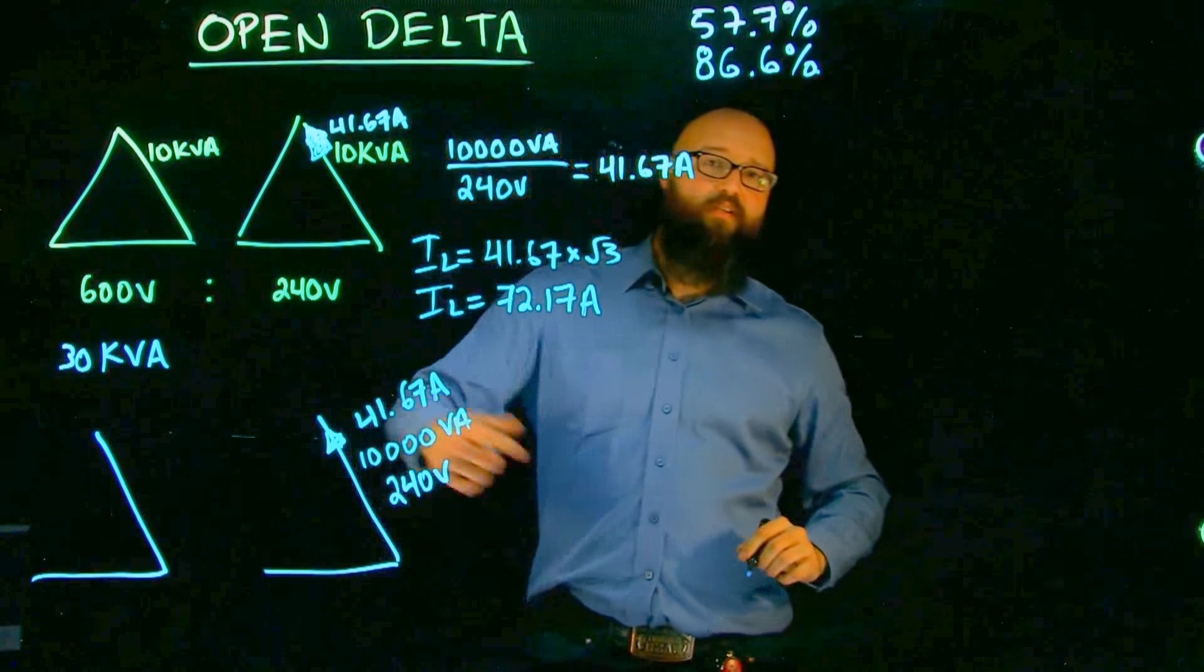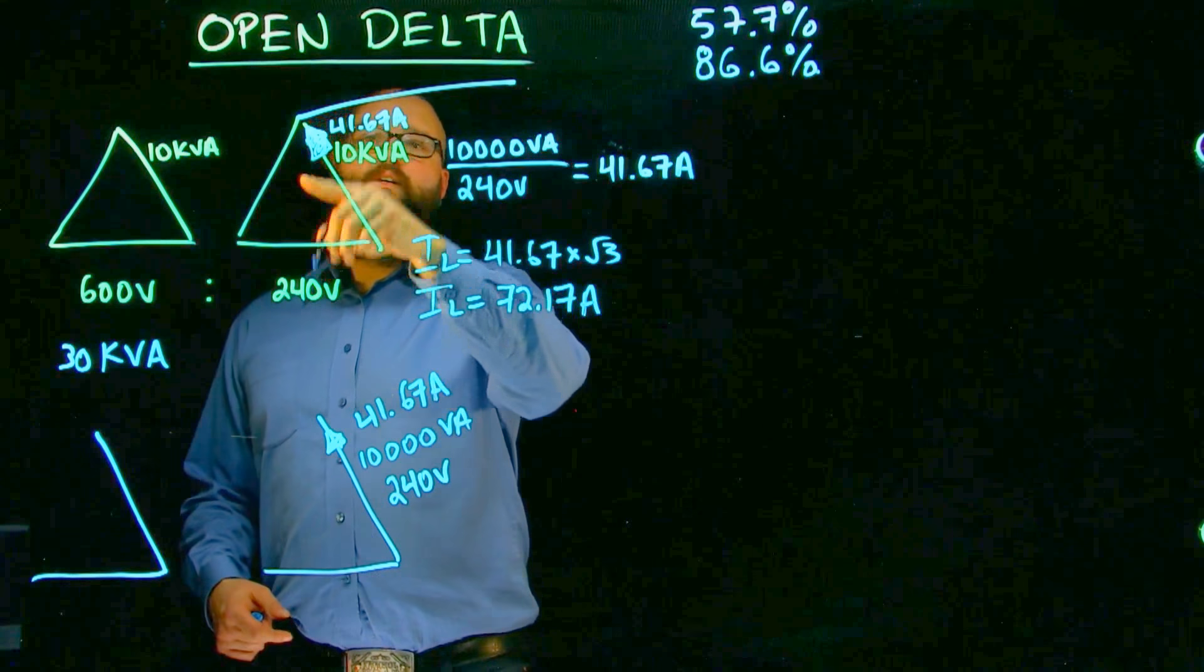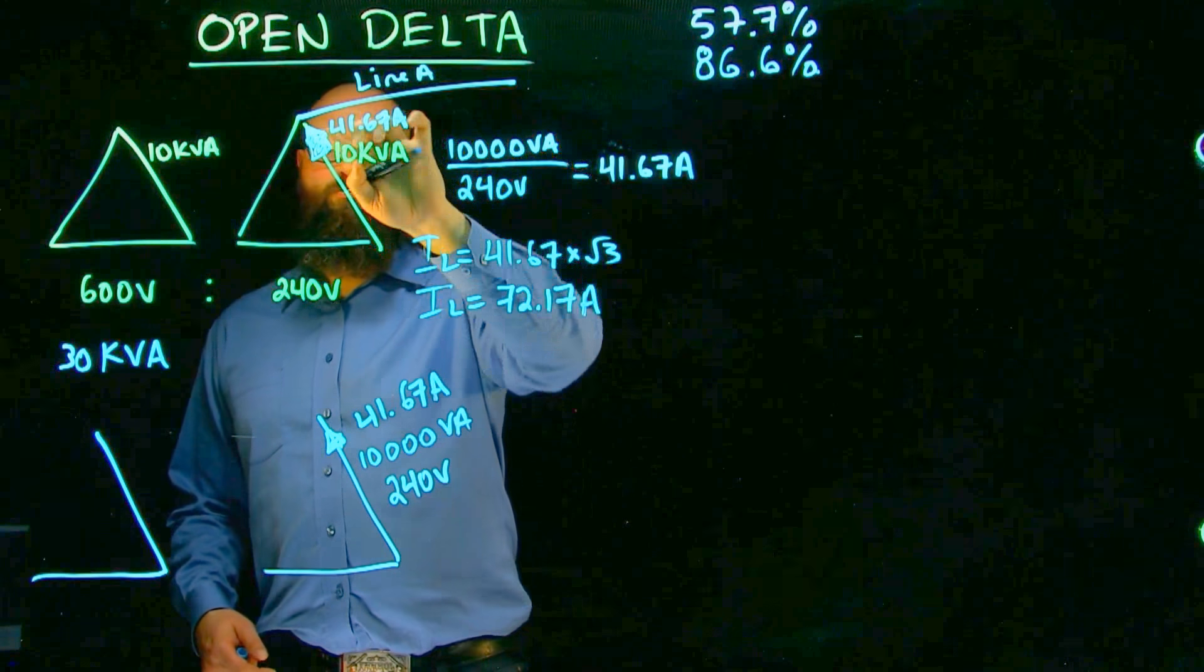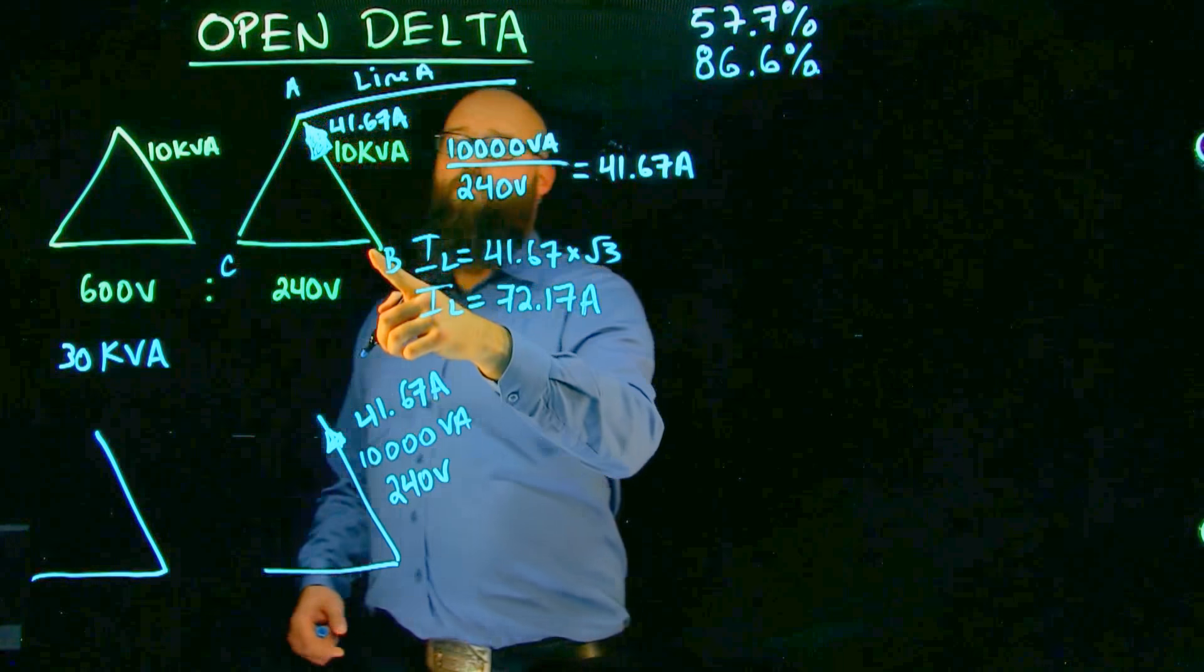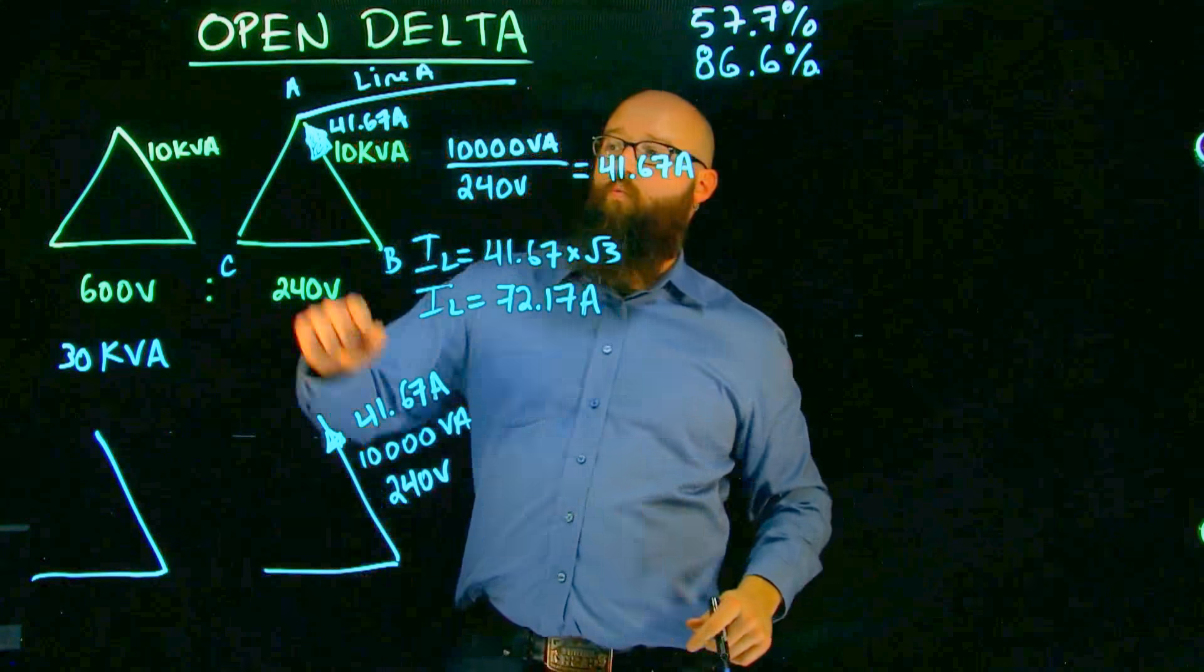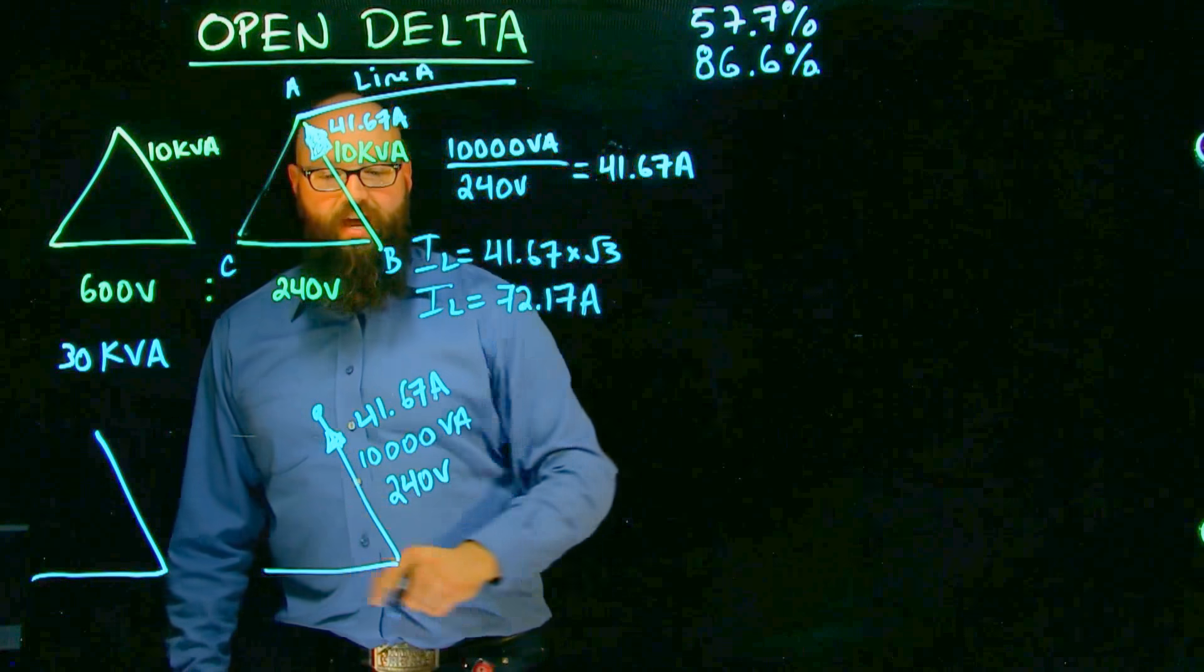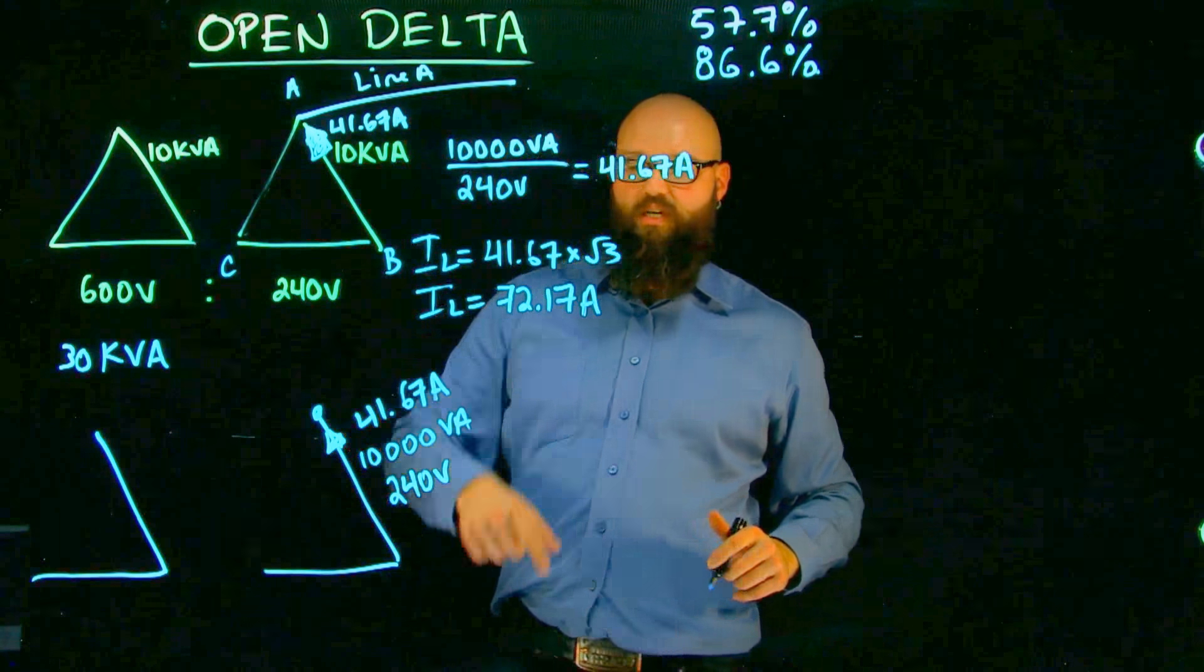But previously, when we had that third leg connected in there, we had, if this was line A, it was composed of, well, we had, I'll go B, C, A up here, we had A to B plus A to C. Okay, when we lose this A to C leg, or our C to A leg, what ends up happening is, we don't have that combination of those two currents anymore. All we have is 41.67 amps.